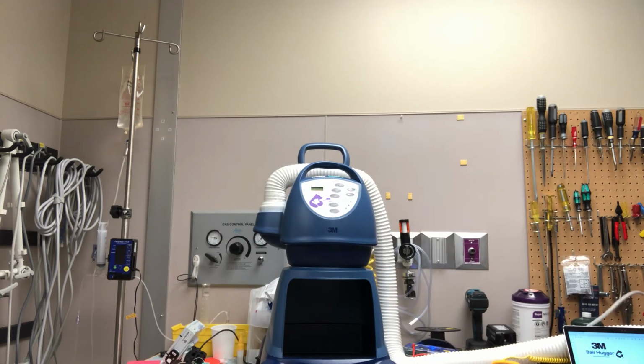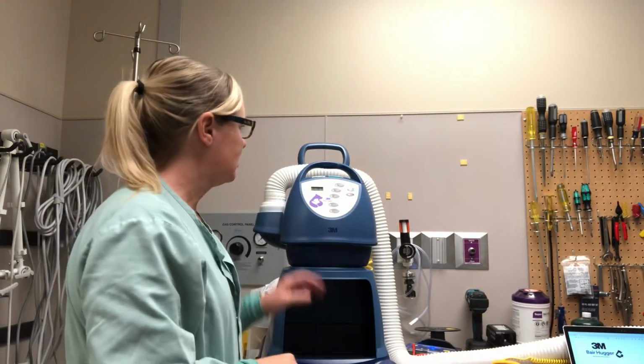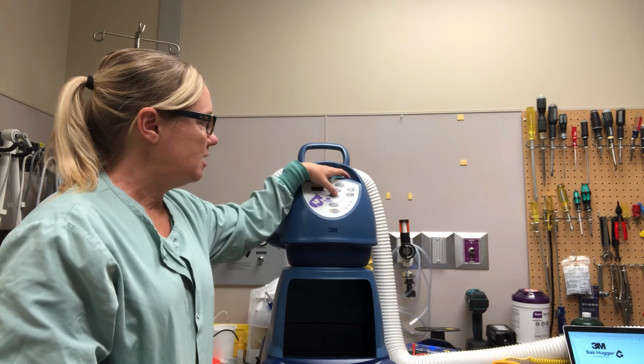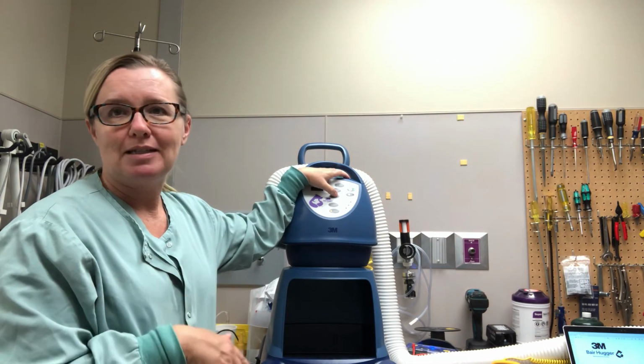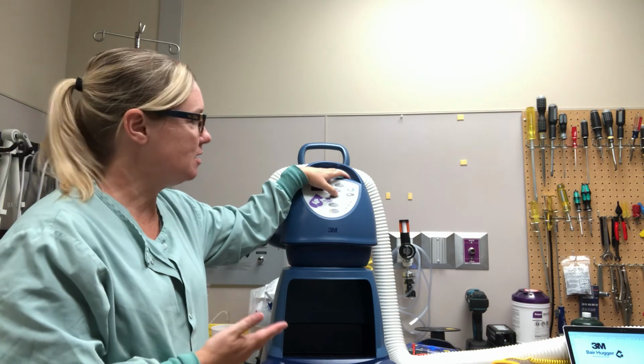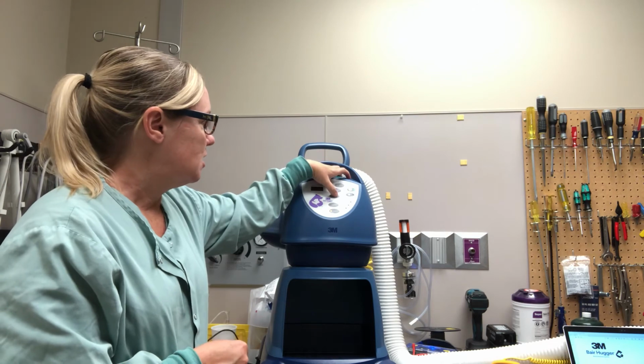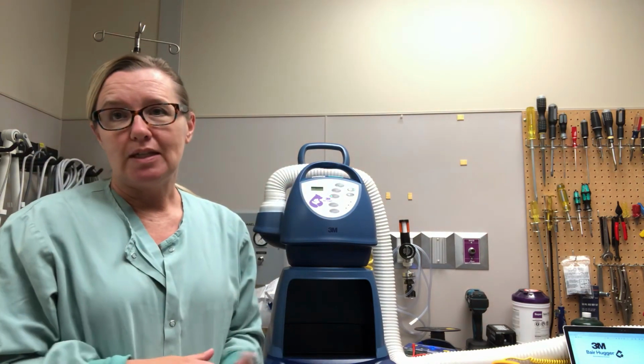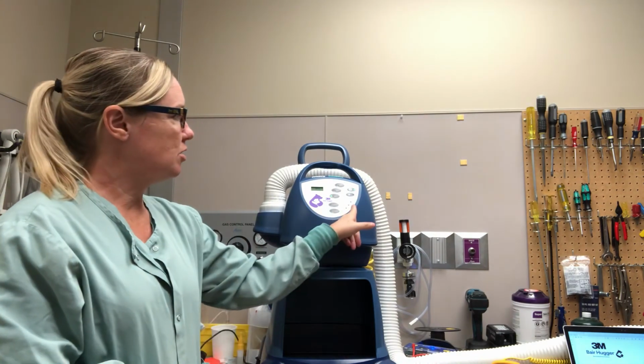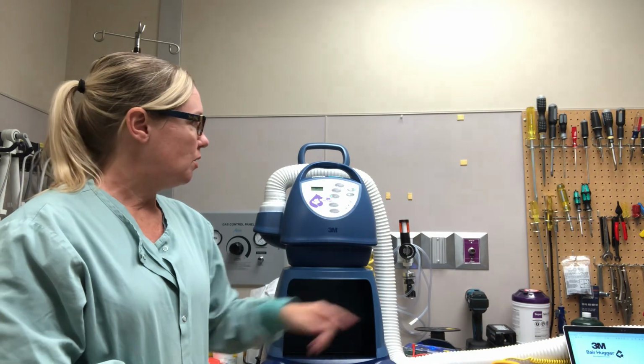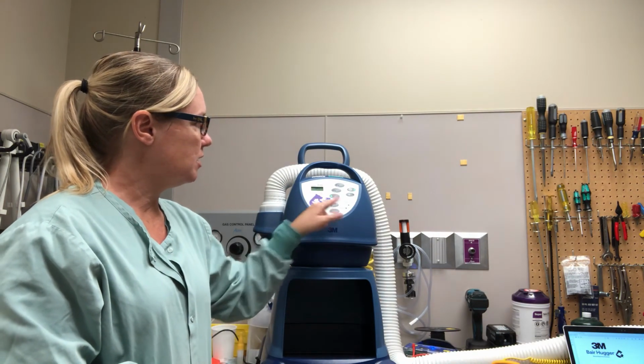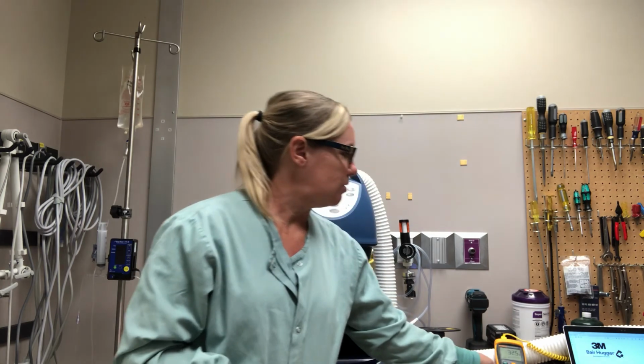So we're going to do that, we're going to unplug. Okay, I'm going to plug it back in. And then, according to the service manual, we need to let it run for about 5 minutes to cool it off, because it did reach that high temp of 49 degrees. So I'm going to set it at 32 degrees Celsius and let it run for about 5 minutes. Make sure I get my temperature and range indicator when it gets to that, and there we go, it just came on. And my meter says 32.6 right now. So that's working very well.